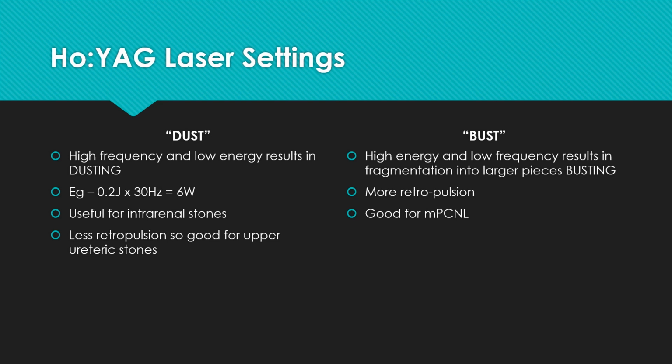The laser settings have a significant influence on laser interaction with stones. High frequency and low energy settings typically result in the formation of dust particles, whereas higher energy and lower frequency settings generate larger fragments. Dusting is desirable when dealing with tricky renal stones through a flexible ureteroscope, when it can be difficult to remove larger fragments.